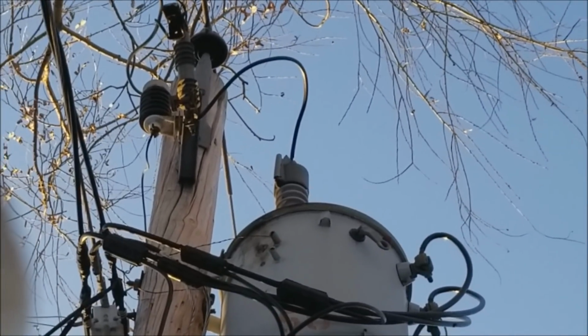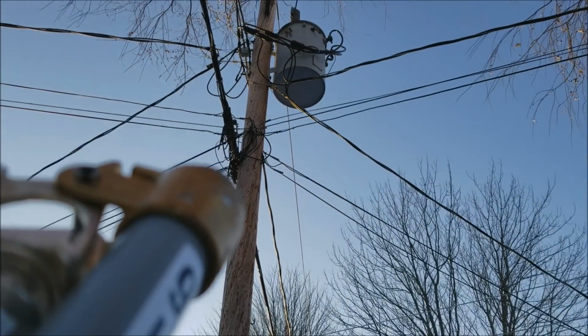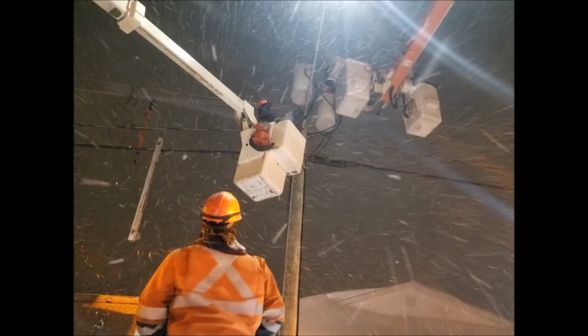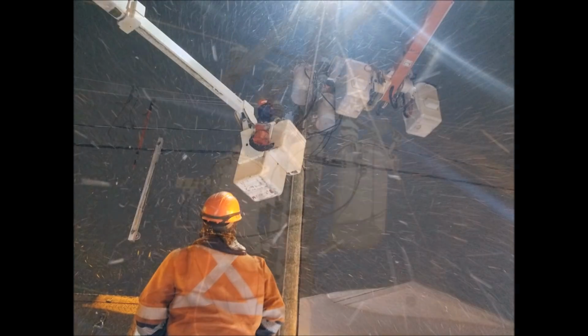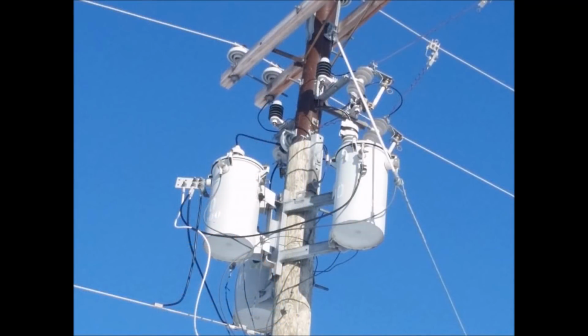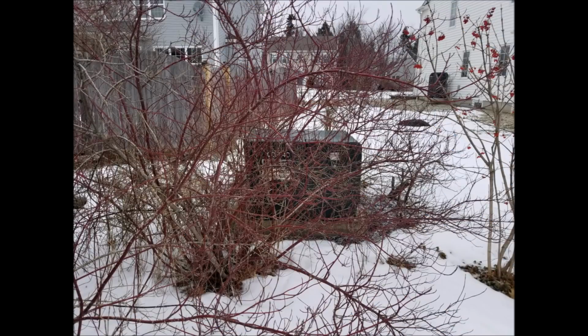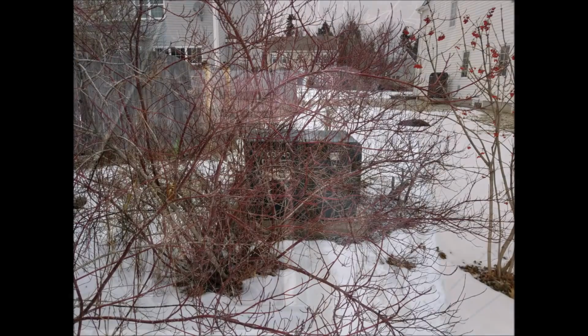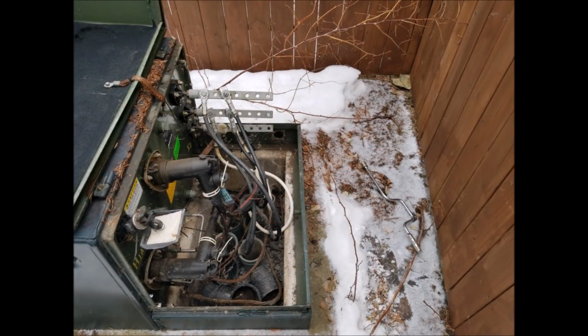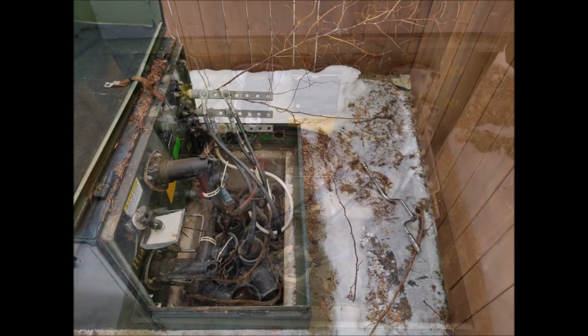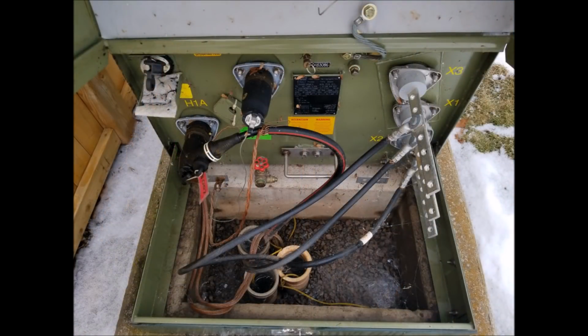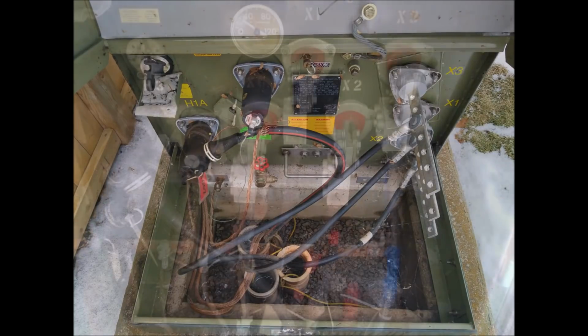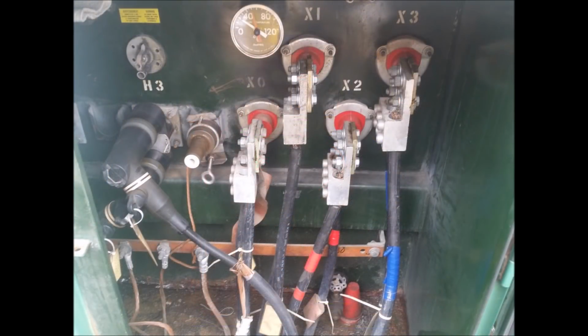When the fuse blows, it is extremely loud and often compared to a gunshot or an explosion. At this point, our system has behaved exactly as it should have. The fuse isolated the transformer before it could blow, although it will have to be replaced. Aside from bad oil, there are many other scenarios which can cause an internal transformer fault. Most oftentimes, when the fuses blow, it is caused by an external fault, such as animals crawling around where maybe they shouldn't be. When these faults occur outside the transformer, we simply need to replace the fuse, and the transformer is left unharmed. There is, however, still a procedure to this, and a few tests we have to do before we can simply close it back in.